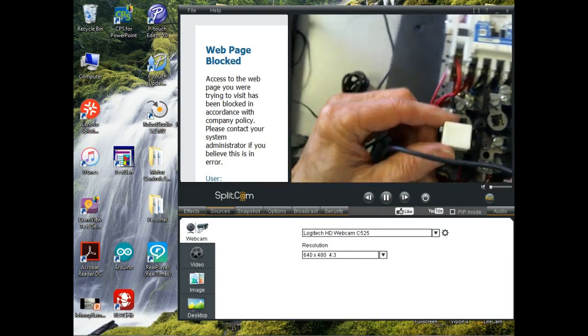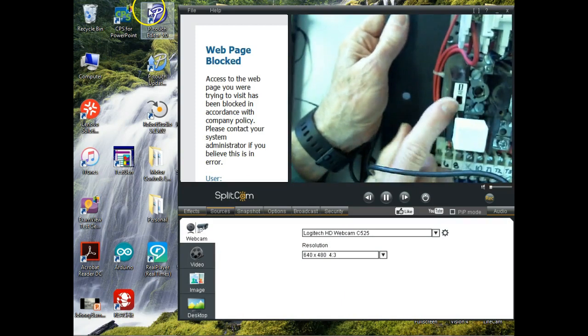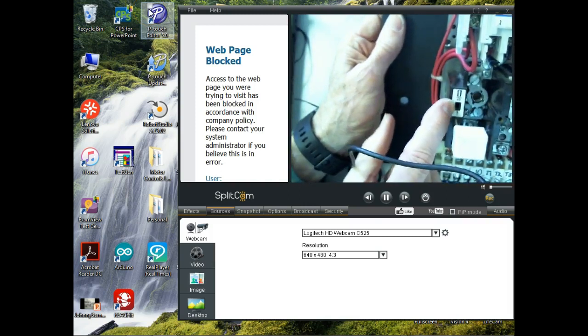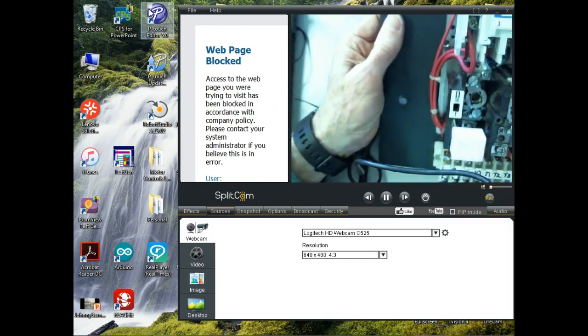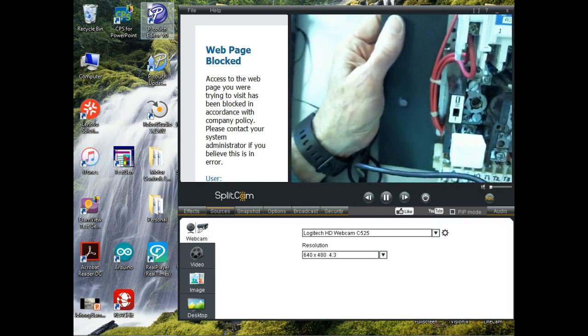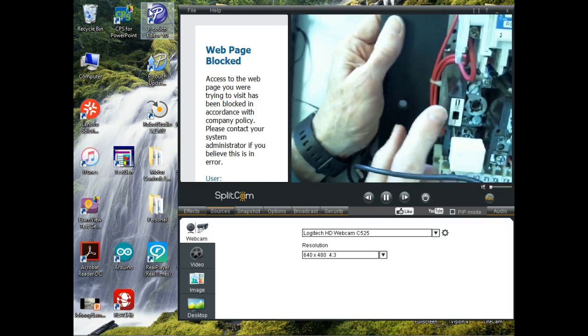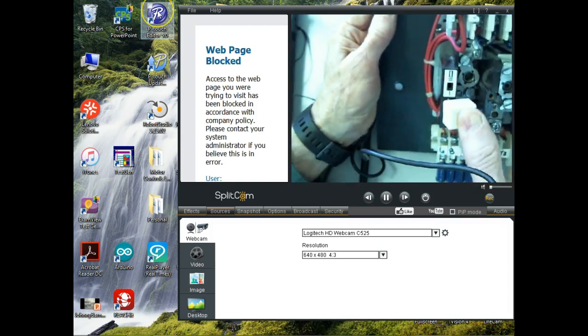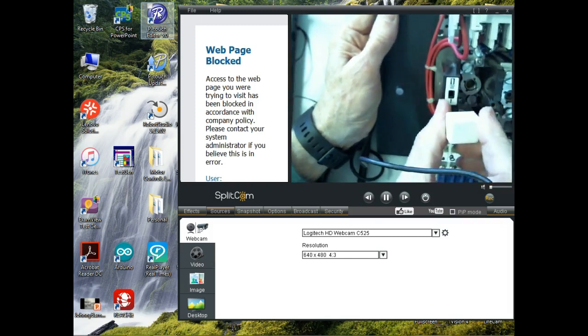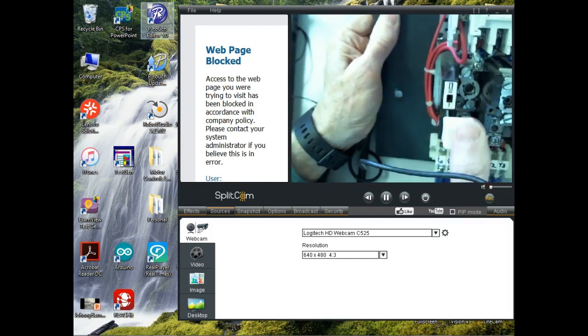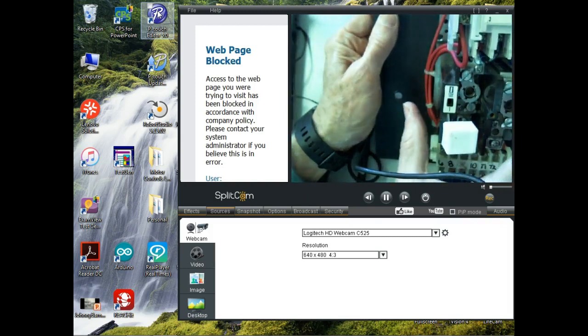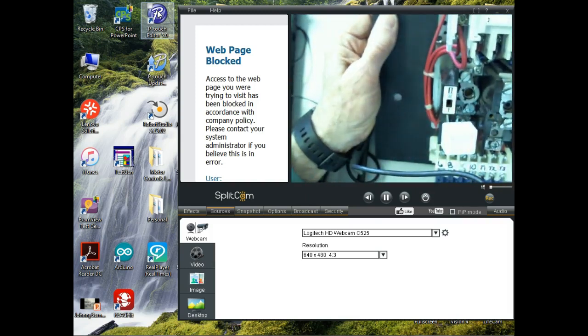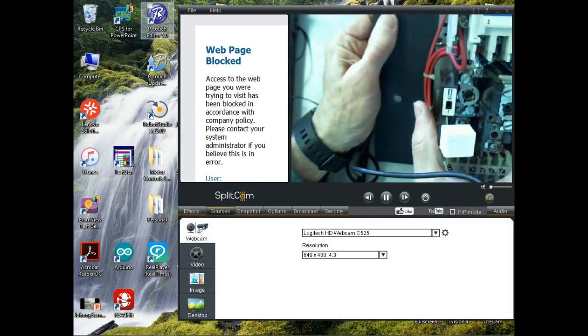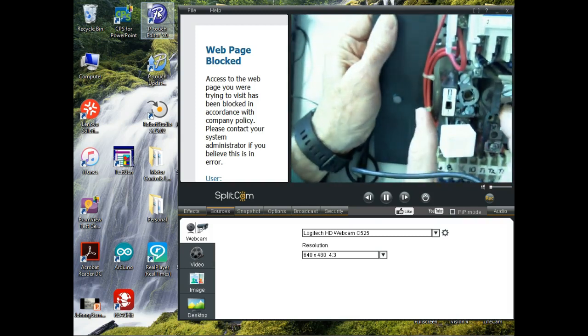So that's what this thing is right here. When this overload trips, this right here would turn red, because you can't tell from the unit if it's tripped. Does that make sense? So if this is ever red, then we have a reset button. And this one's been bent too. We have one reset button that resets all the wheels. That makes sense? Everybody okay? So these are the ones that we've got.